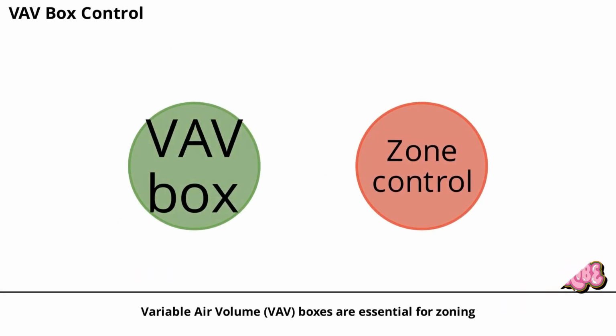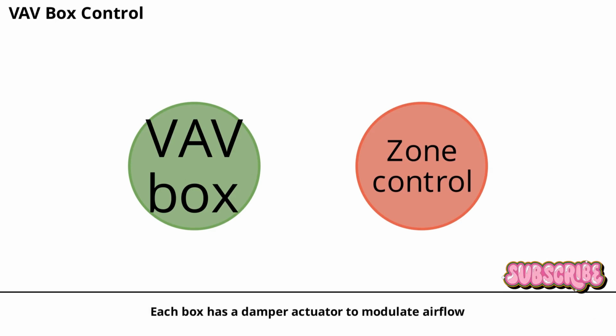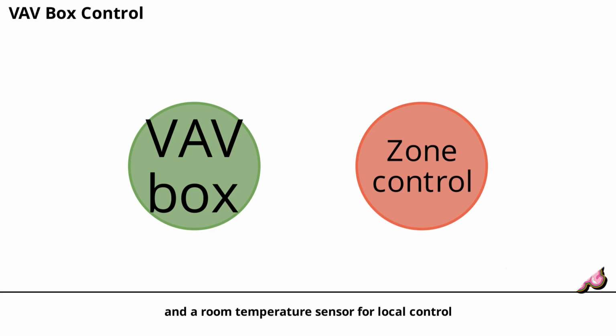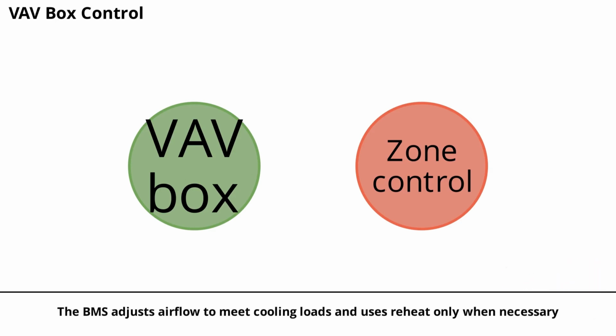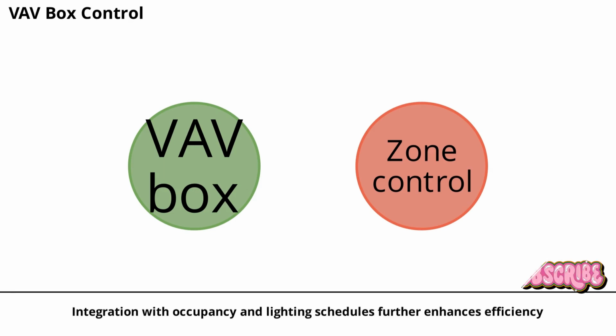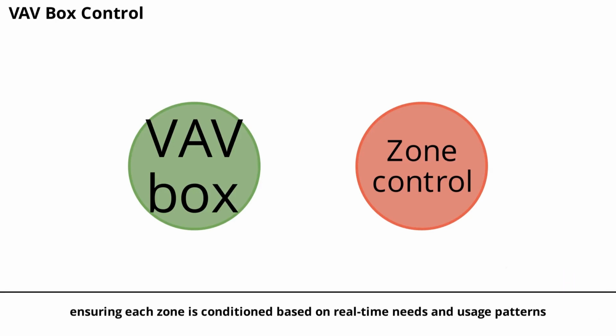Variable air volume, VAV, boxes are essential for zoning. Each box has a damper actuator to modulate airflow, a reheat coil valve for added heat, and a room temperature sensor for local control. The BMS adjusts airflow to meet cooling loads and uses reheat only when necessary. Integration with occupancy and lighting schedules further enhances efficiency, ensuring each zone is conditioned based on real-time needs and usage patterns.